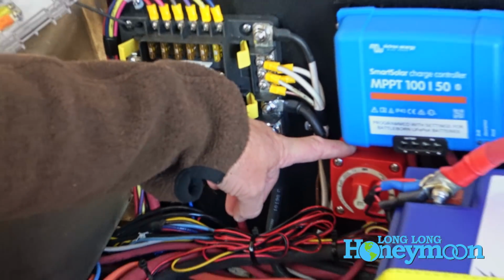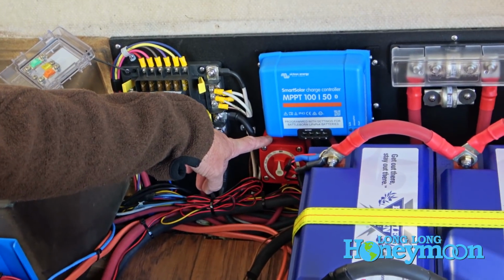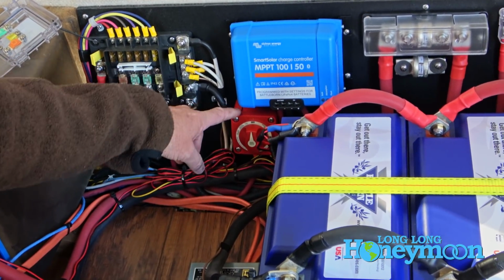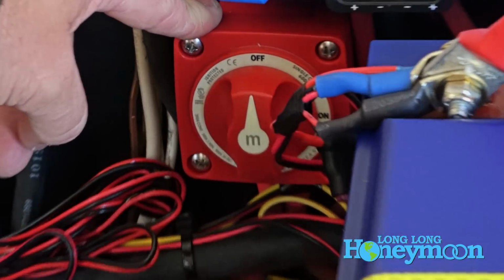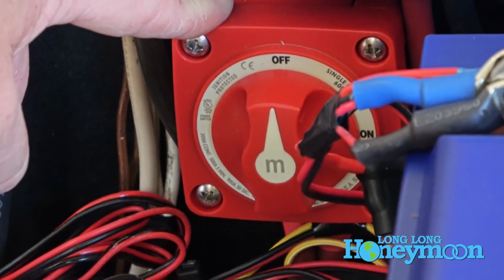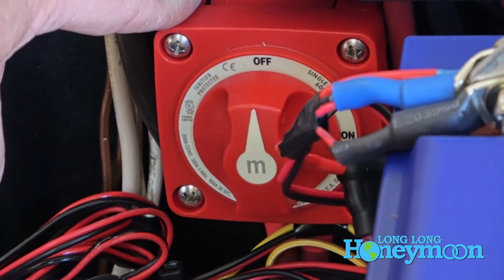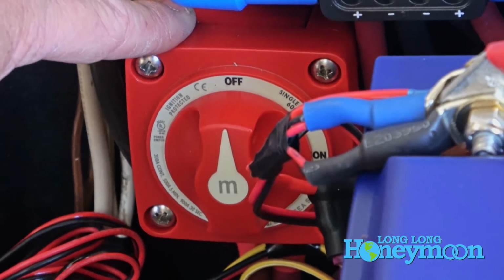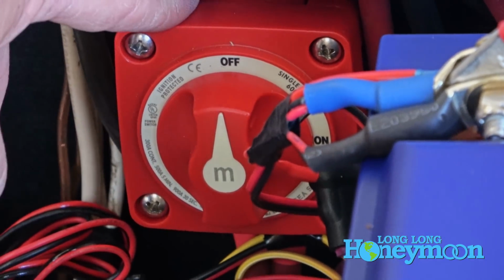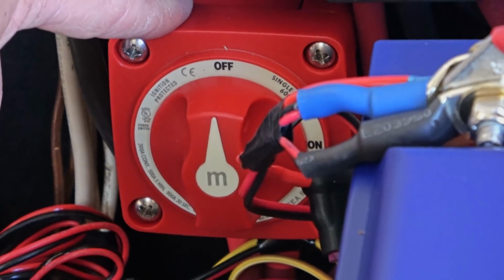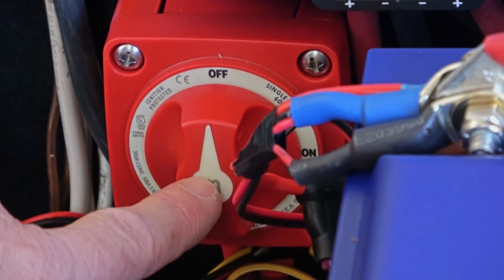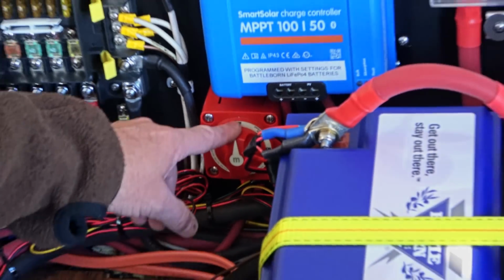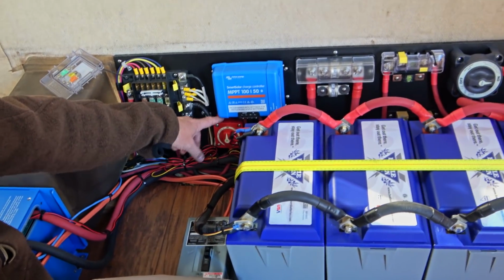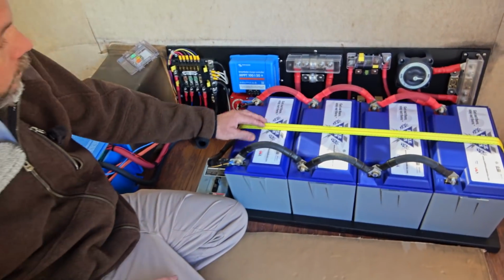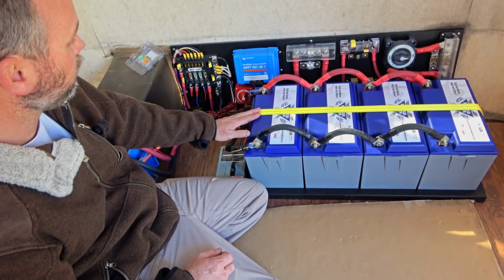This switch here is a Blue Sea 300 amp switch, our disconnect switch for the solar panels on the roof. Because the solar panels put out continuous voltage anytime they're exposed to sunlight or light, you need a way to remove that power from the system. This switch gives us the ability to do that — we can turn it off, and the power will be removed from the solar controller and won't continue to enter the rest of the system.